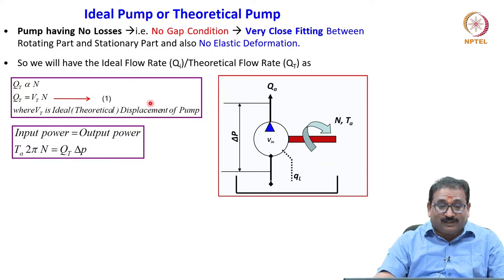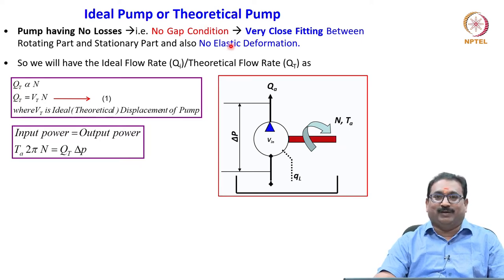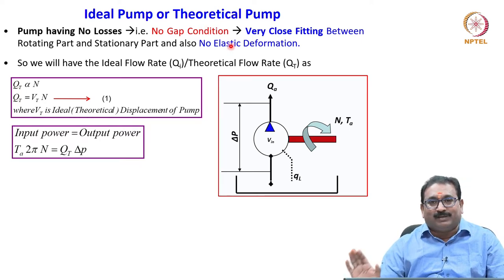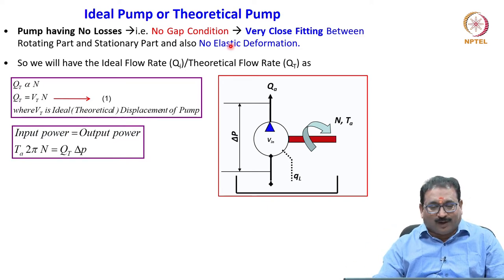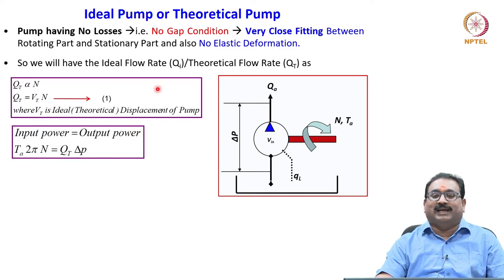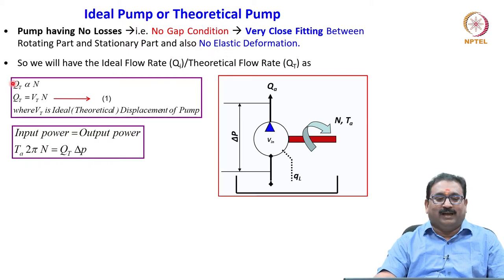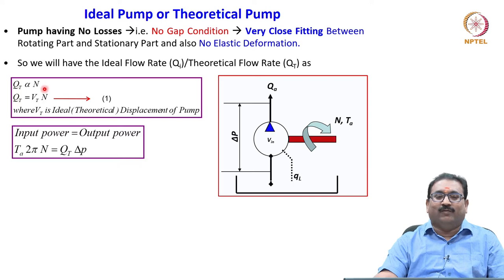This is the ideal pump. Please remember: the ideal pump has no gap condition and no elastic deformation. But all pumps are not ideal — there is always a clearance and always elastic deformation. Assuming no gap condition and no elastic deformation, the theoretical flow is proportional to N, equal to VT into N, where VT is the ideal displacement of the pump.